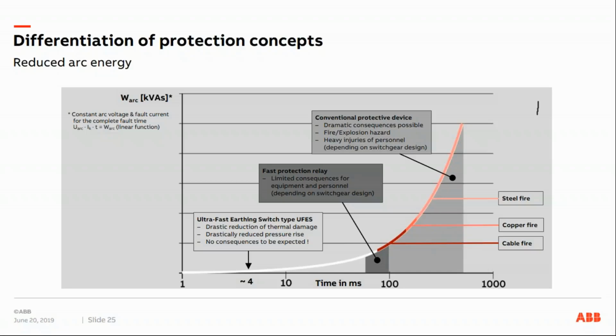Here on this graph, what you can see is the energy development over time in case of an arc fault. What we're seeing here is that for conventional protection devices, the energy level develops in such a way that you will have dramatic consequences on your equipment. There will be fire, explosions, hazards, as we could see in the second video, which I showed you. There might be, or hopefully there won't be, which is still possible, heavy injuries of your personnel, depending on the switchgear design. The other one, the fast protection relay concept, has limited consequences for your equipment and personnel.